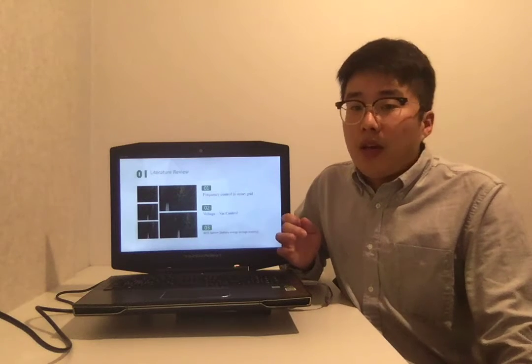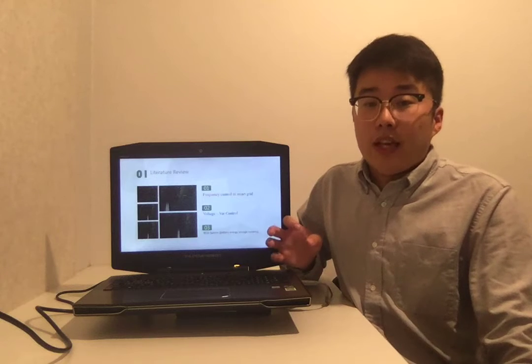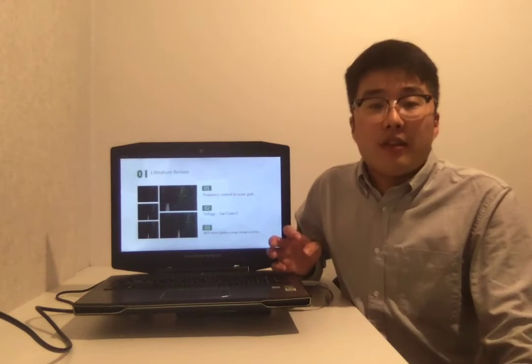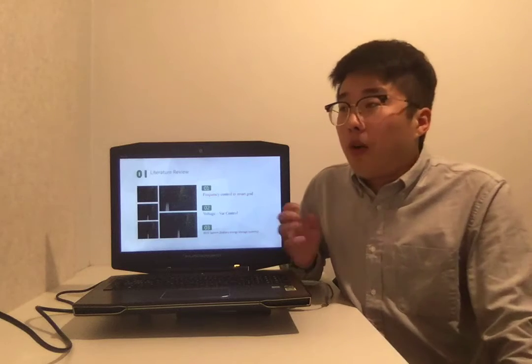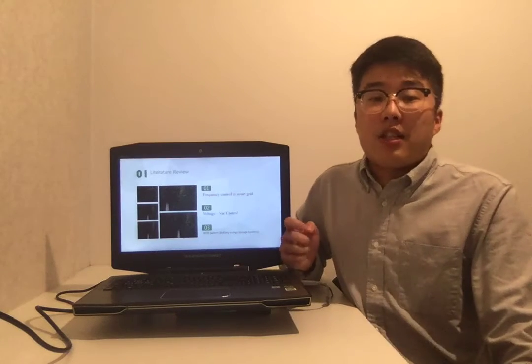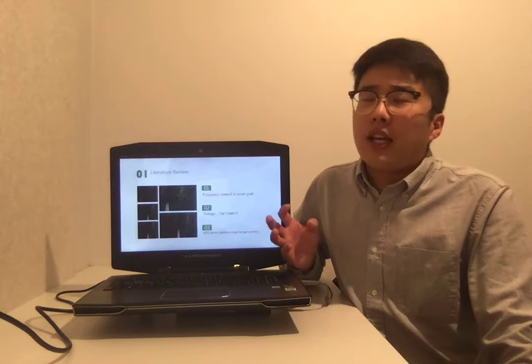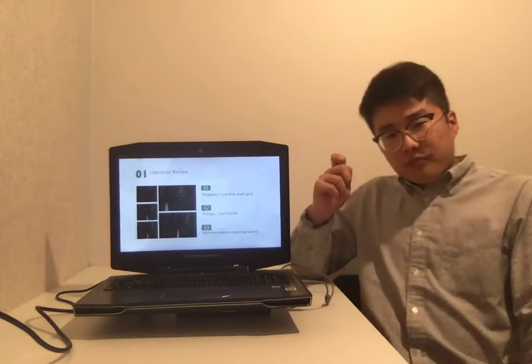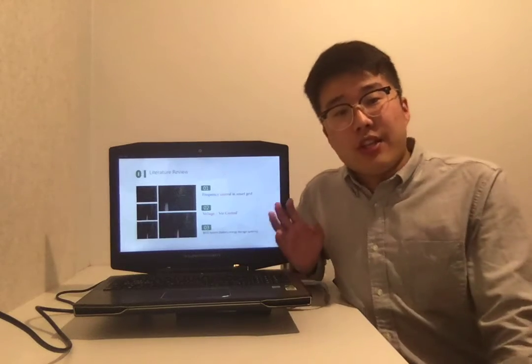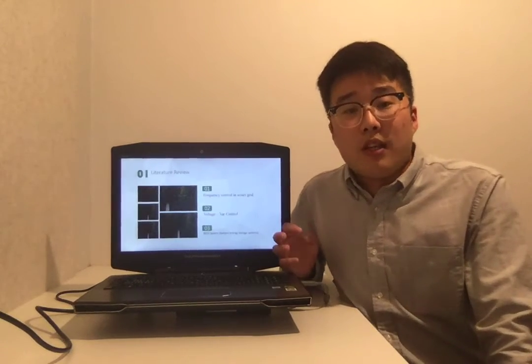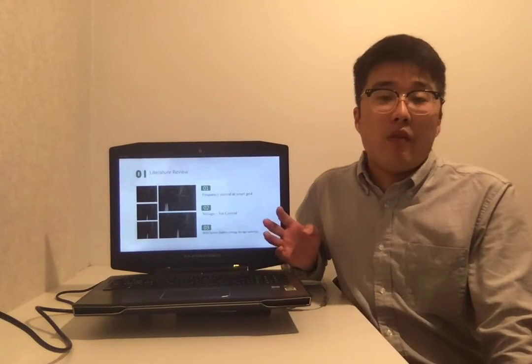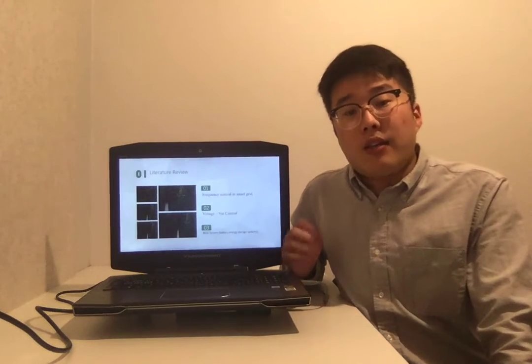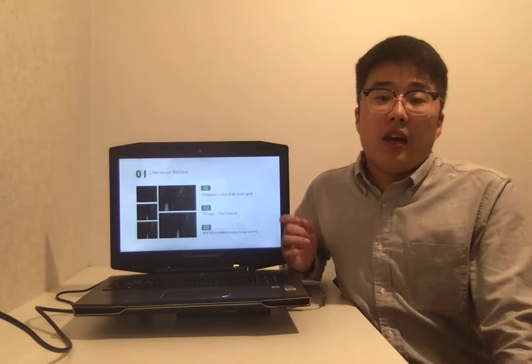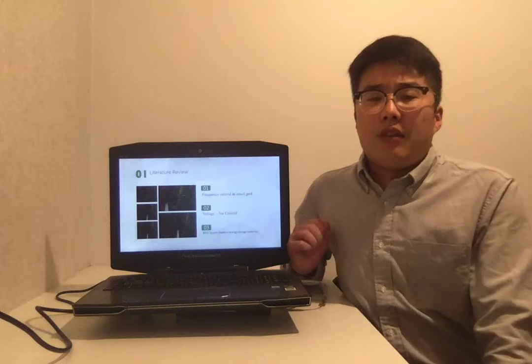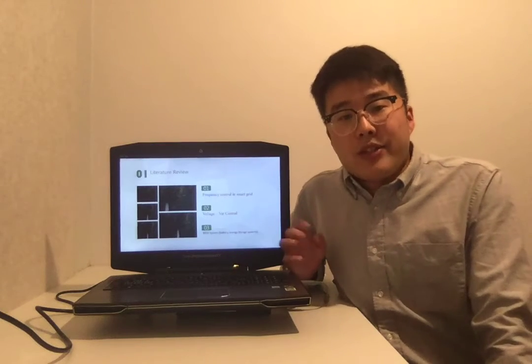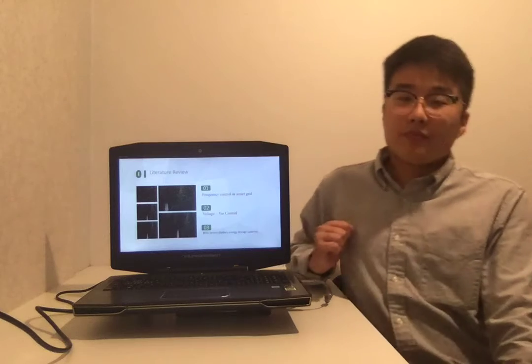This method is economically efficient and very easy to maintain, and does not impose an economic burden on the users in the grid, such as increased electricity cost and so on. However, the disadvantage of this method is that when the motor and the transformer in the grid operate at very low power, the capacitor bank tends to overcharge the entire grid. As a result, the voltage quality in the power grid is damaged, affecting all users in the grid.